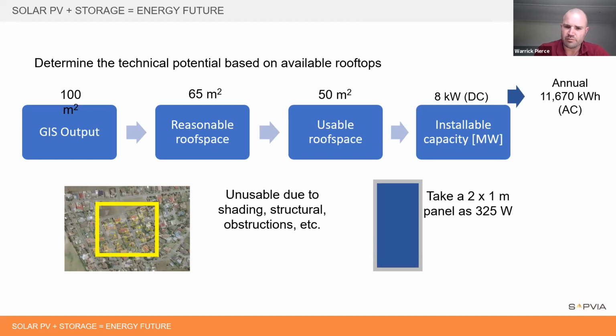So we took a certain size PV panel, a certain rating, 2x1 and a 325 watt panel, which is actually pretty much the panels I've got on my own roof. And then we say, okay, what does that translate to in terms of installable capacity? So how many panels can you pack on your roof, which then gives you 8 kilowatts in this example, which then based on the specific yield, the average of the region, around a 20% capacity factor, gives you 11,670 kilowatt hours, obviously on the AC side.